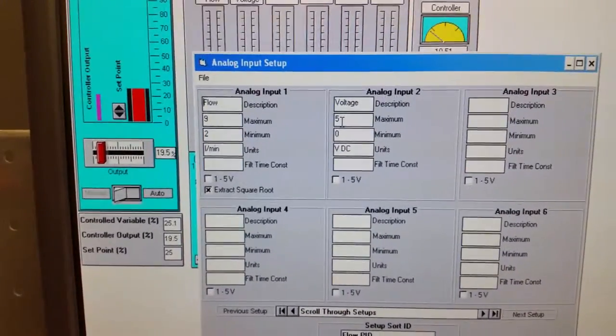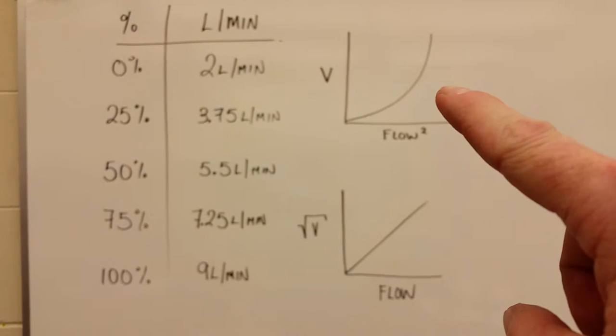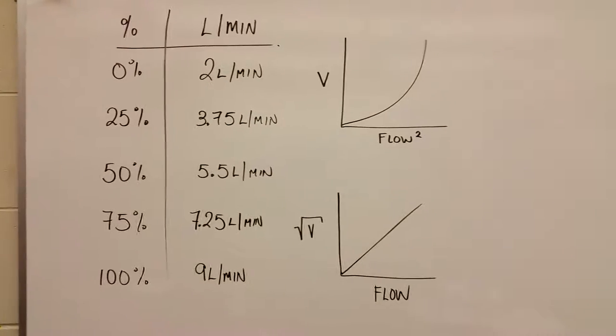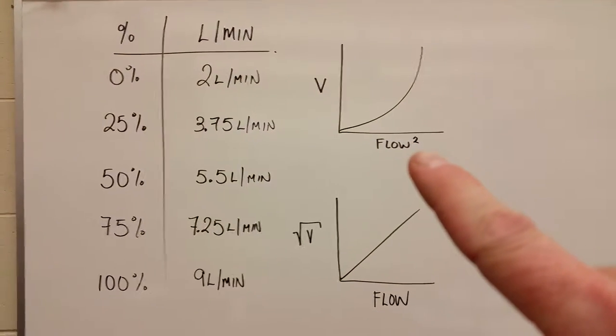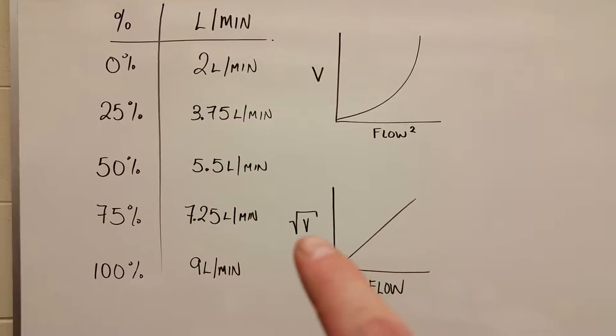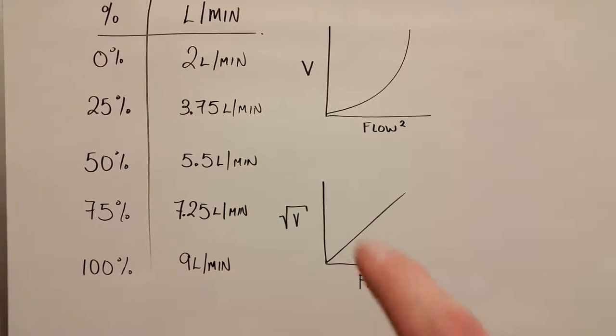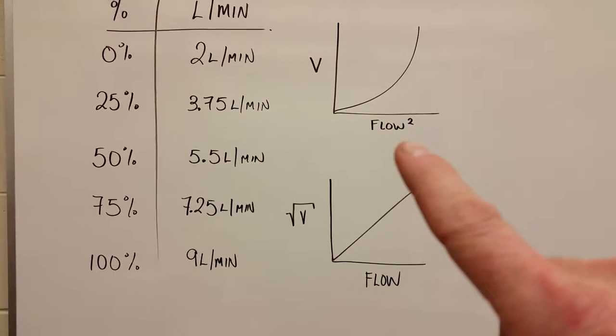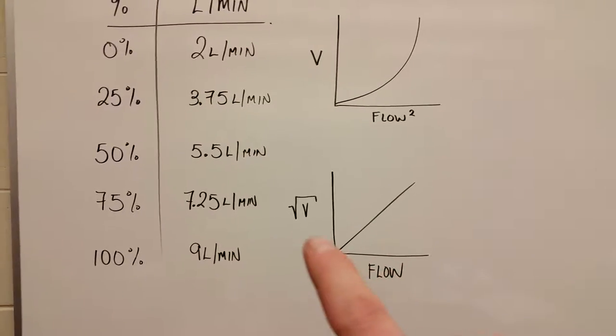The zero-to-five volt DC voltage gives us an exponential curve output. We need to take the square root because that voltage corresponds to the square of the flow. Whatever we do to one side of the equation we do to the other — to get rid of the square we take the square root, which gives us the flow.